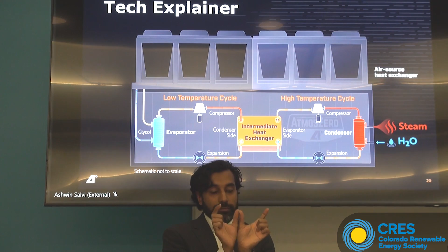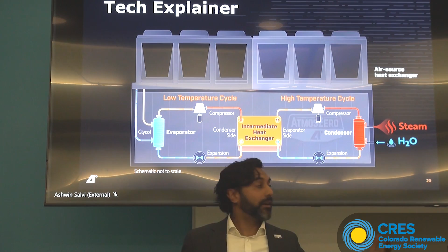So we have a cascaded system - two heat pump loops tied together. As this gas is converting to a liquid, this liquid is turning to a gas - it's a dual phase change heat exchanger. That lets you get the lift, the temperature, from ambient air all the way to steam temperatures.